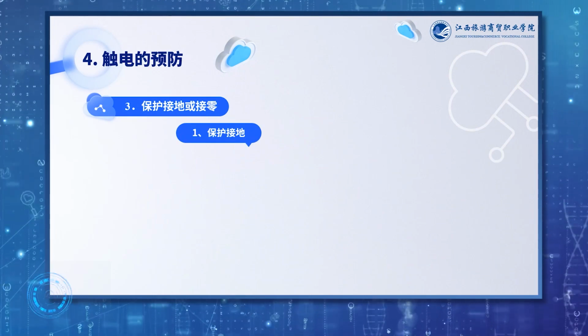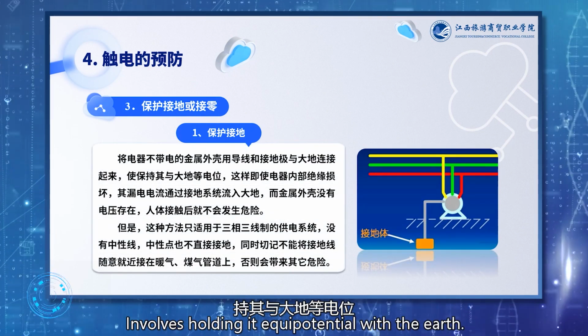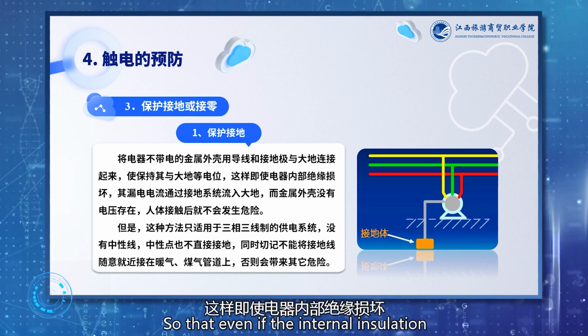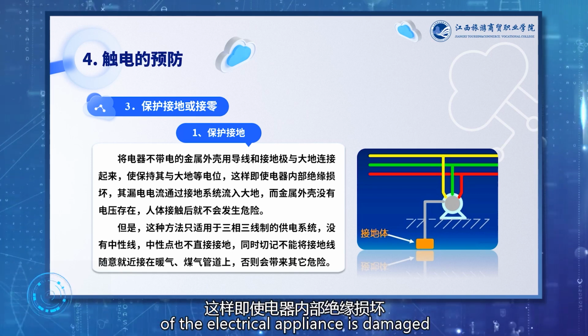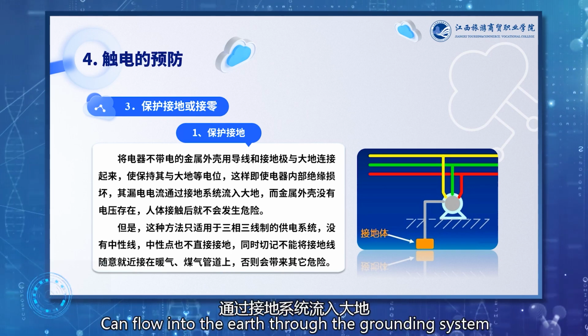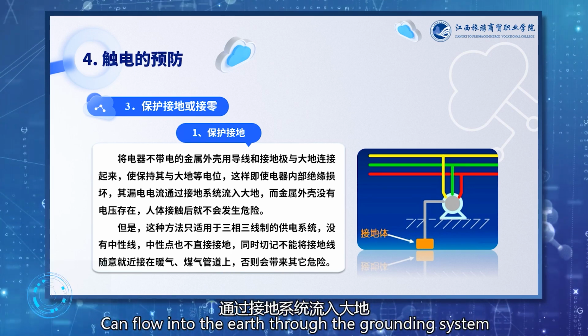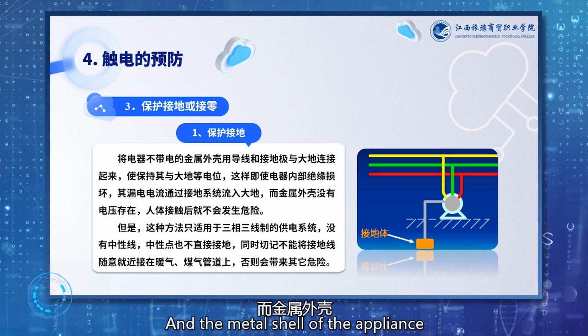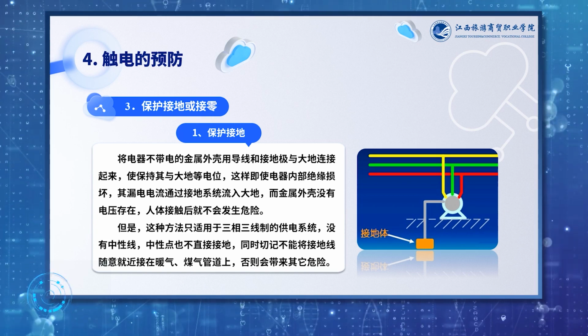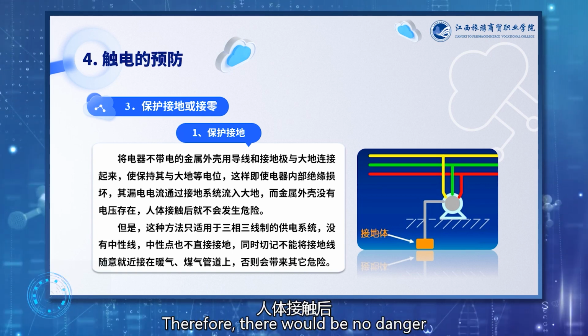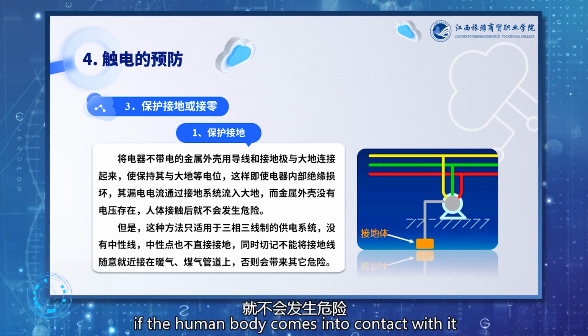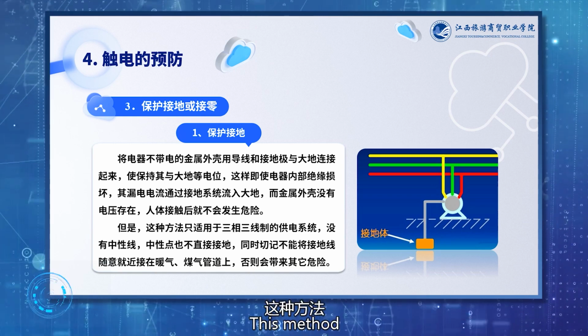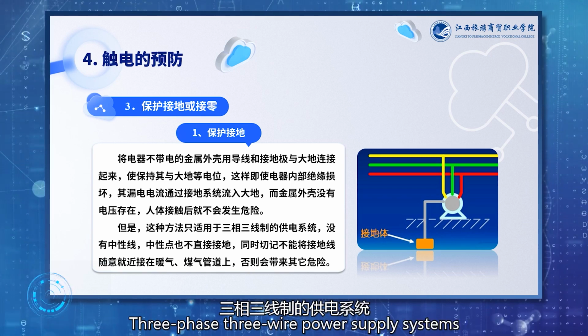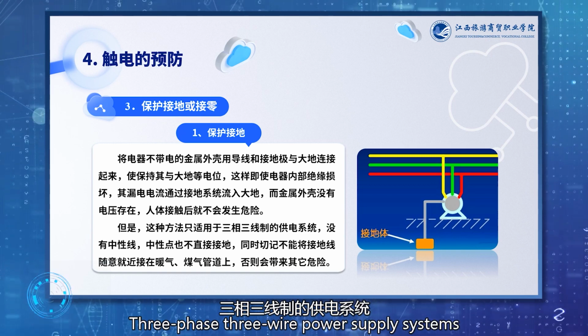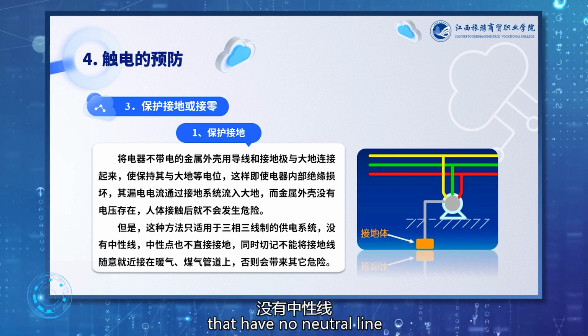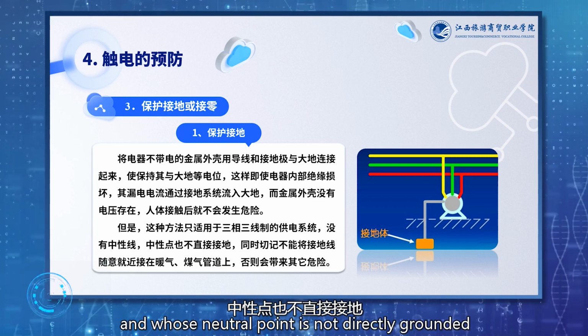Protective grounding involves holding it equipotential with the earth so that even if the internal insulation of the electrical appliance is damaged, its leakage current can flow into the earth through the grounding system, and the metal shell of the appliance will have no voltage. Therefore, there will be no danger if the human body comes into contact with it. However, this method is only applicable to three-phase, three-wire power supply systems that have no neutral line and whose neutral point is not directly grounded.